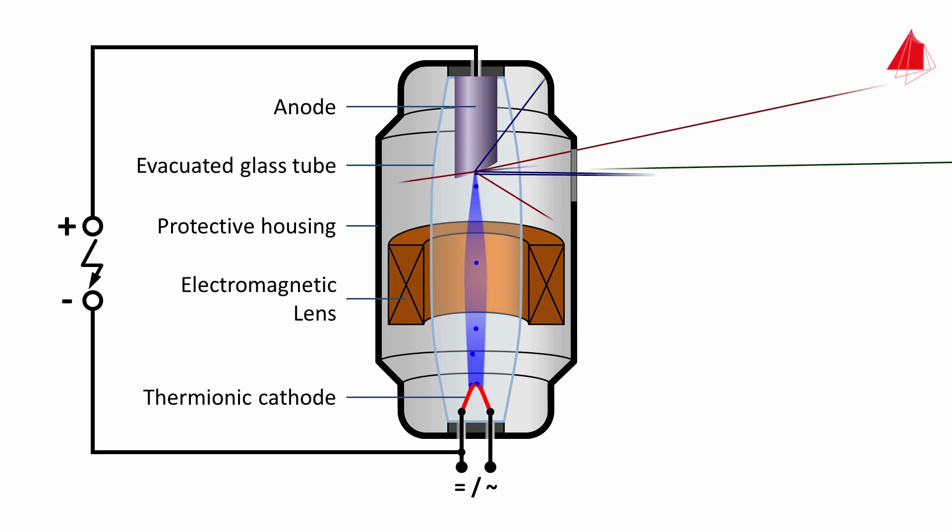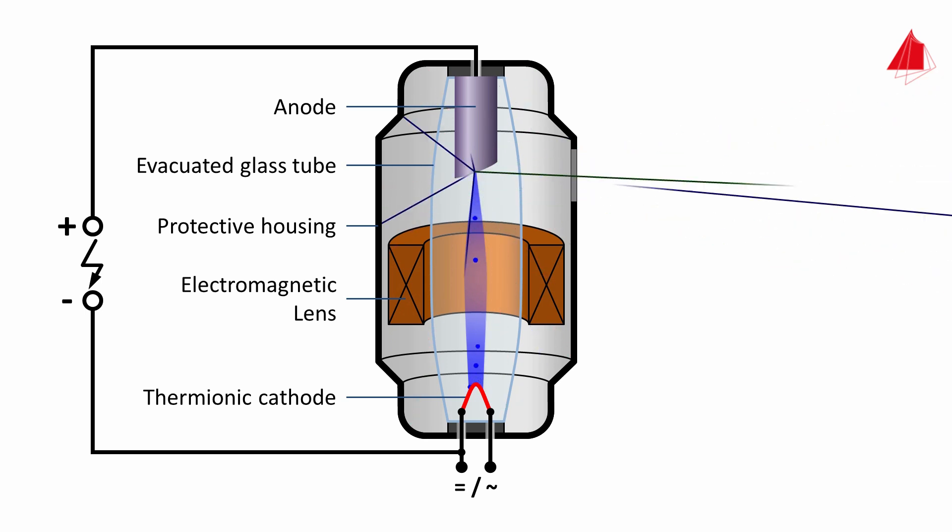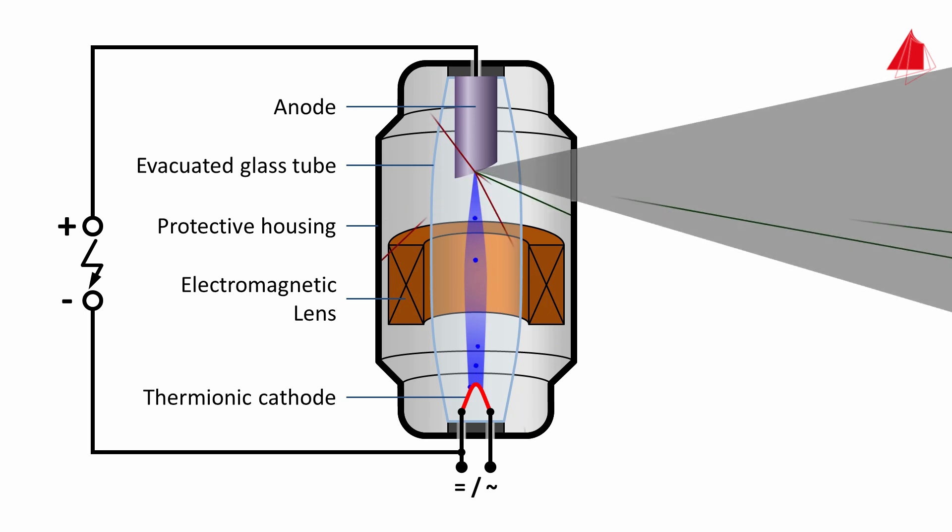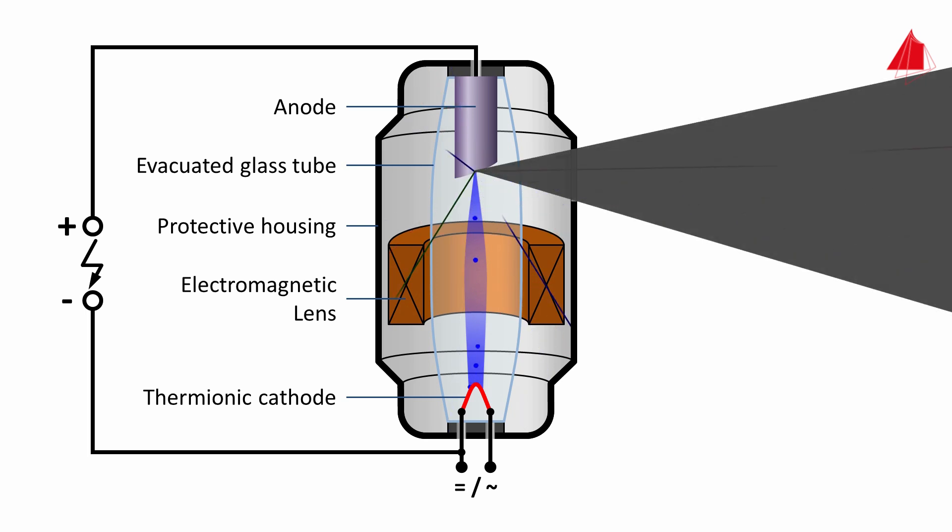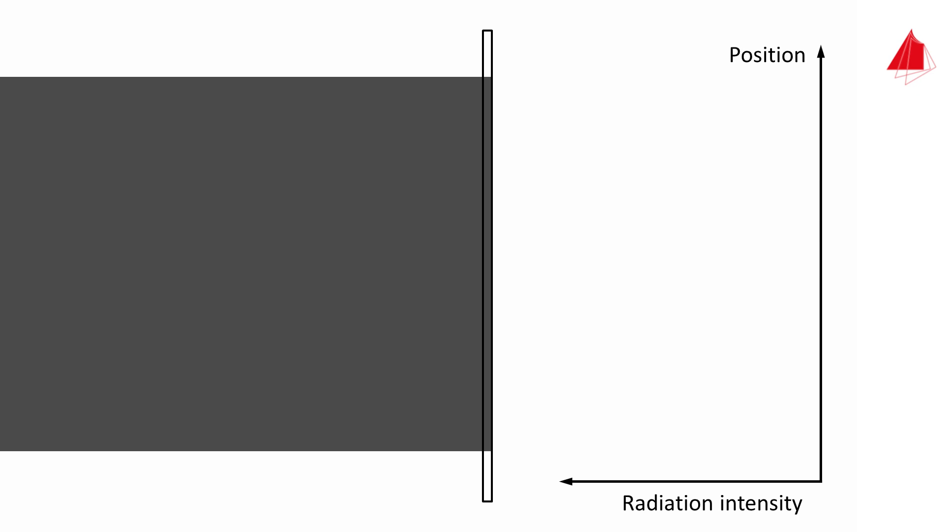Now how are x-ray images actually produced? For an easier understanding, we will first depict the usable x-ray radiation as a grey cone and then simplify it as a parallel beam. To take an x-ray image, a suitable image capture unit is needed. This can either be a conventional x-ray film which turns darker the higher the intensity of the radiation, or it can be a digital detector field that measures the intensity of the radiation and converts it to electrical signals. When the radiation intensity is plotted as a function of the position, a uniform distribution is the result. At each point the image capture unit records the same radiation intensity.